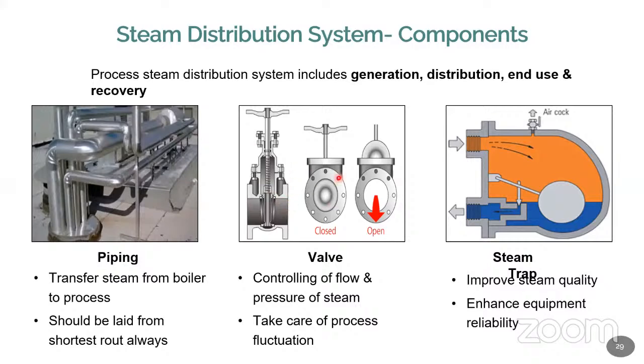That's called a PRV, pressure reducing valve. That will reduce my pressure from 7 kg to 3 kg, and you can take a separate line for the 3 kg pressure. So these valves and regulating valves are mainly used for regulating the flow as well as pressure. Mostly pressure, but flow is also regulated. So this valve also has to be taken care of, because sometimes it's a mechanical component, and sometimes there is a weakness in the system. Because of that, steam loss is going to take place.